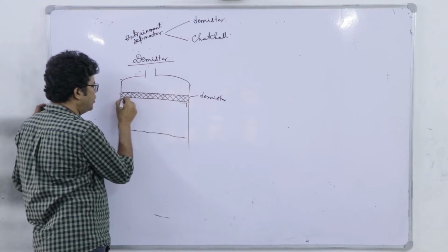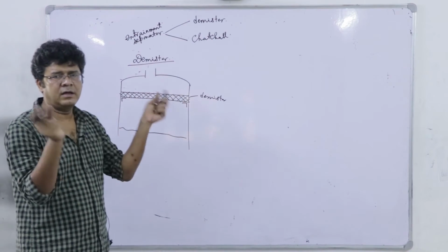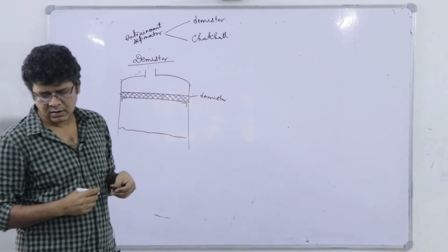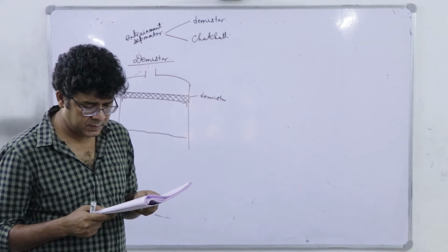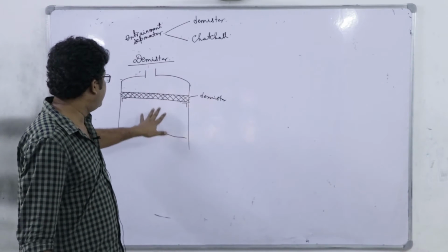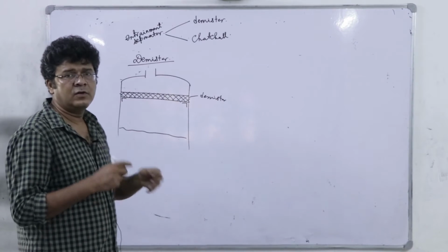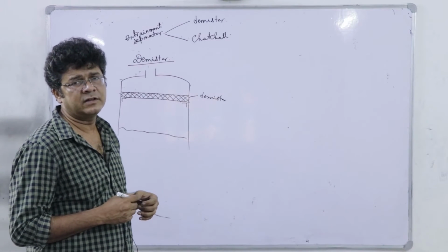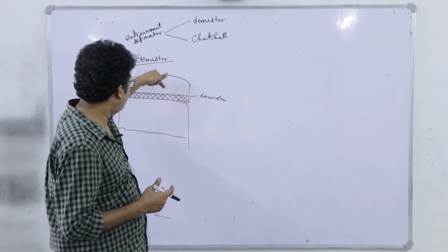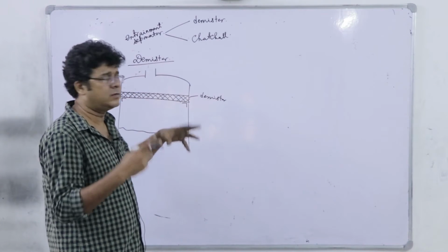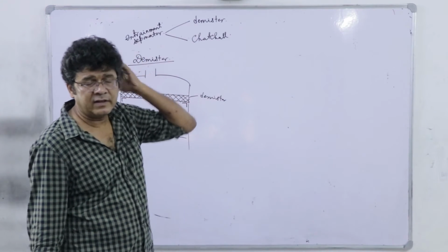And we have support, it's circular cross section, right. We have this T-angle circular beam on which it's resting. So you see that whenever the entrained liquid droplet and the vapor pass through this wire mesh, what will happen? Because of interfacial tension, the liquid droplet will be trapped within the cage of this wire mesh, and definitely it will coalesce with adjacent liquid droplets and fall back to that liquid pool, whereas the vapor will pass. So that is called demister.